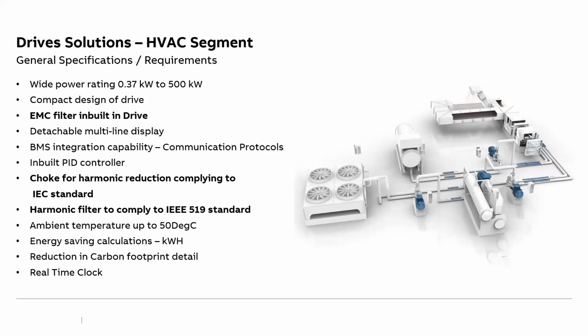Then the choke is basically the harmonic filter, based on the different IEEE 519 and other regulations which are there. We need to comply with that. Ambient conditions in terms of the temperature, like if it is 50 degrees, 40 degrees, whatever the temperature, the VFD should be suitable for those ambient conditions. In terms of altitude also, 1,000 meters is normally what most VFDs are suitable for. Plus it should have the additional coating.